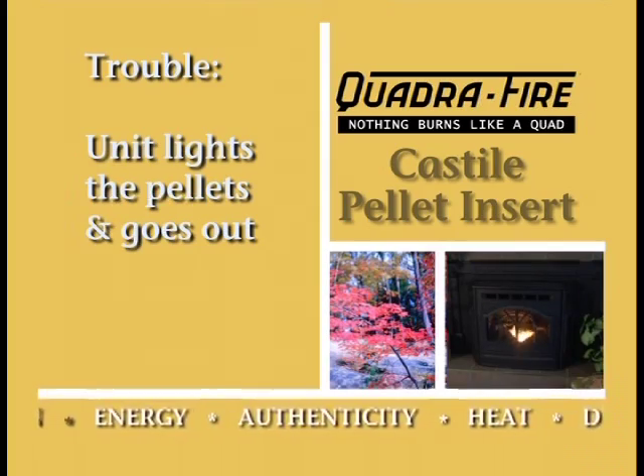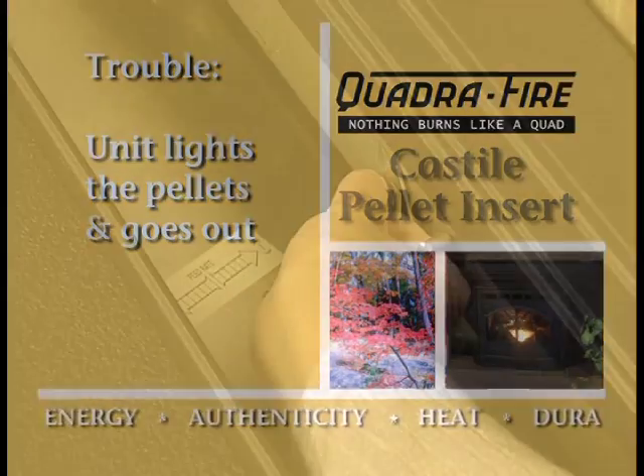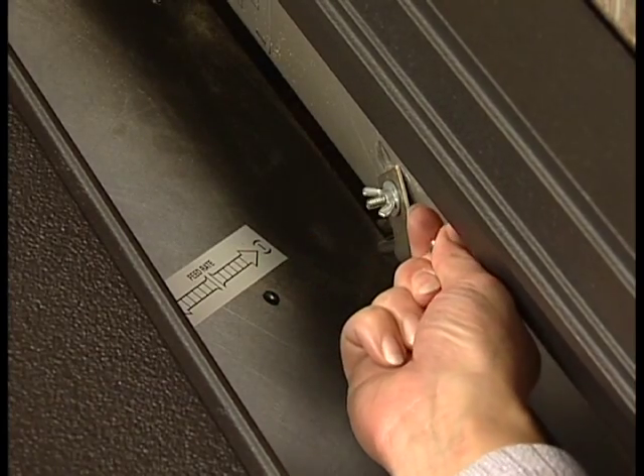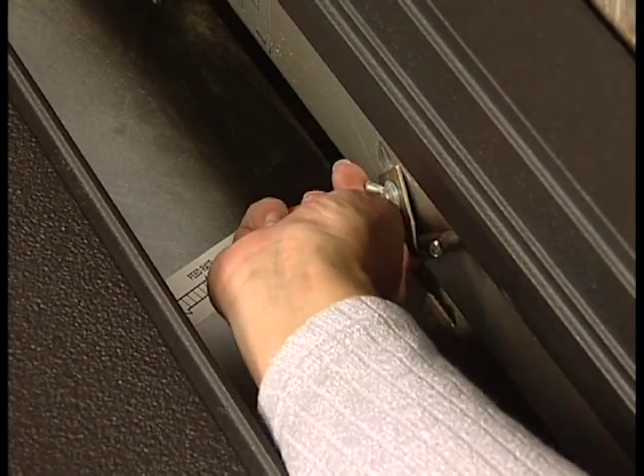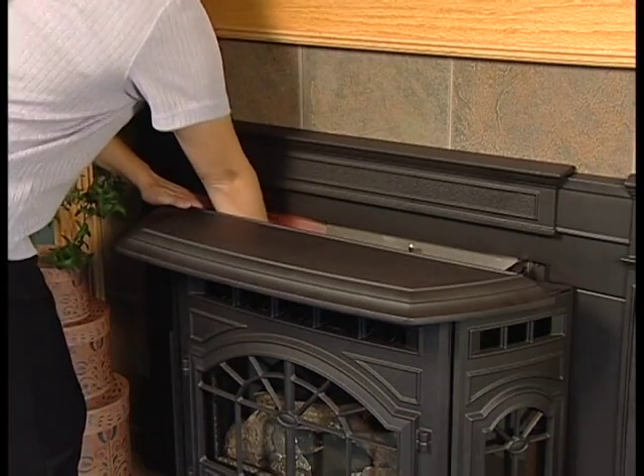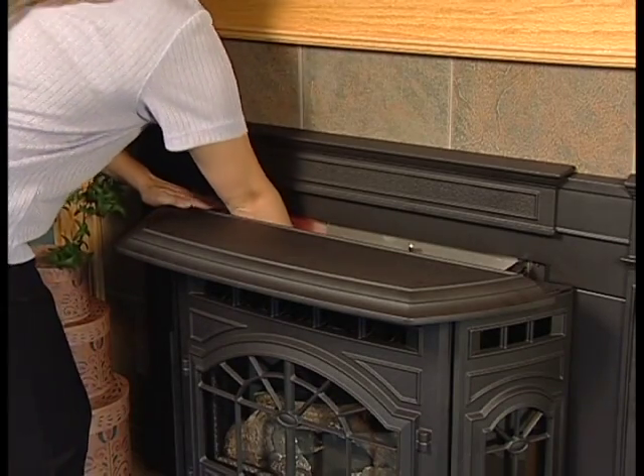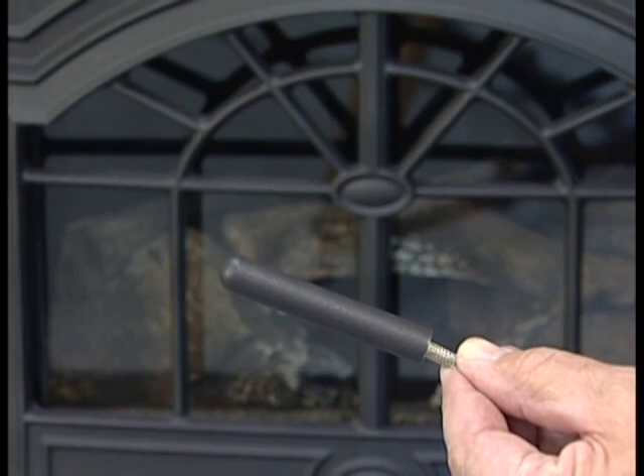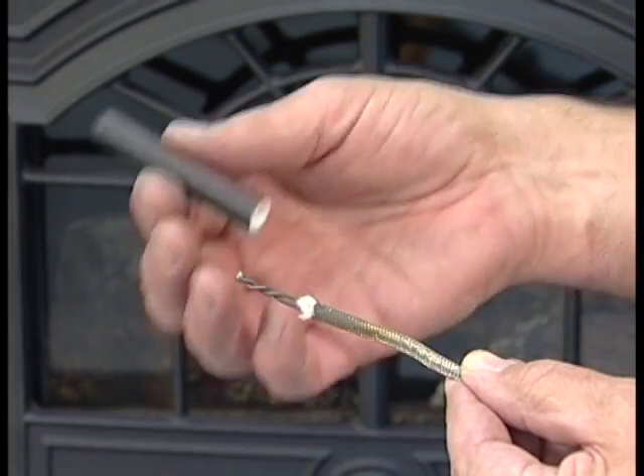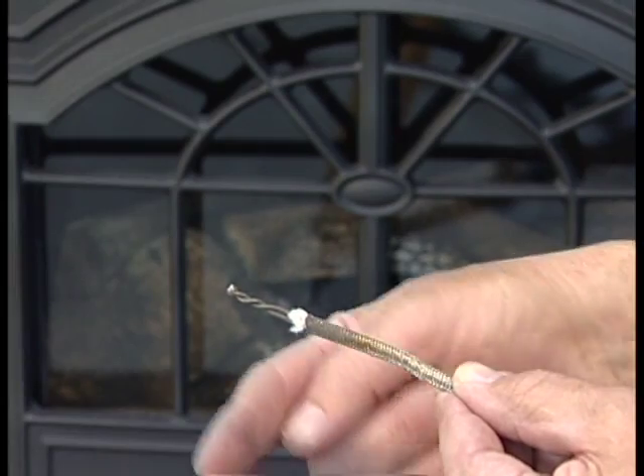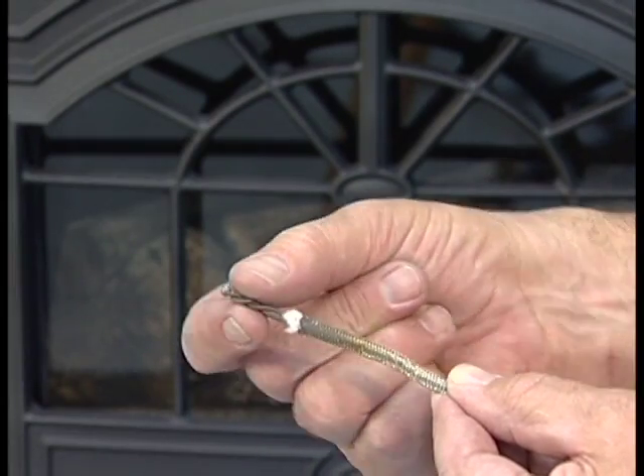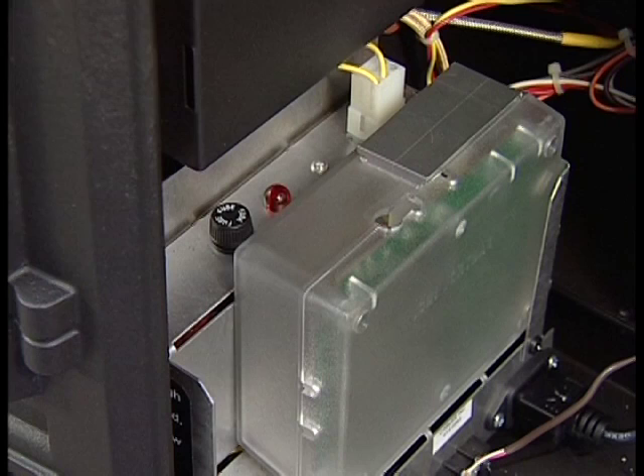The unit is lighting, but the fire goes out. Check the feed adjustment plate in the hopper. If the plate is not open enough, it will not allow enough fuel to drop into the fire pot. Check the thermocouple wire. Remove the protection tube and inspect the thermocouple. If the wire is fractured, replace the thermocouple.